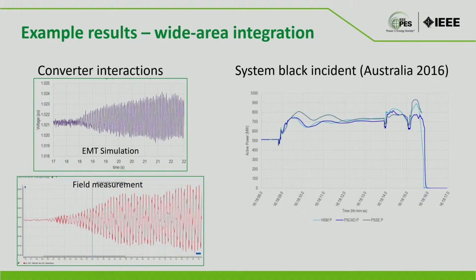This is called the wide area integration approach. So this was like an entire region model in EMT, model in RMS, apply the disturbance as it happened on the field, and then see how it's responding. So you are actually validating the entire region, not one plant, but every plant, but only for that disturbance, right? One on the left hand side is a converter interaction - you can see what the EMT model picked up, and what was the reality on the field.